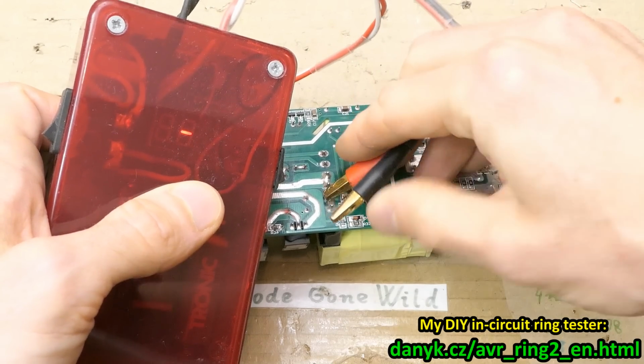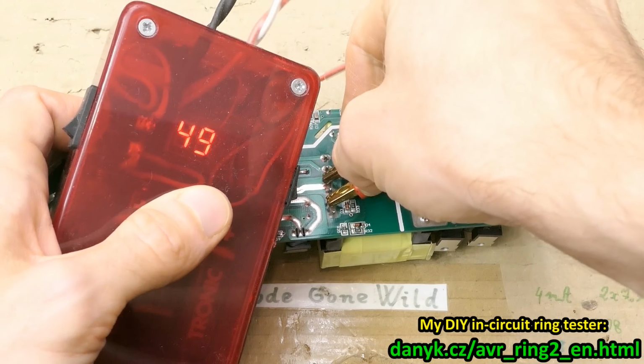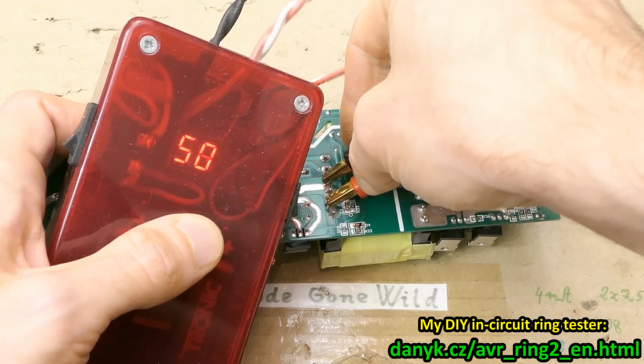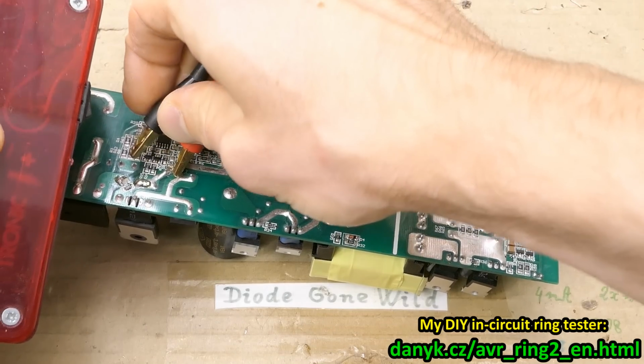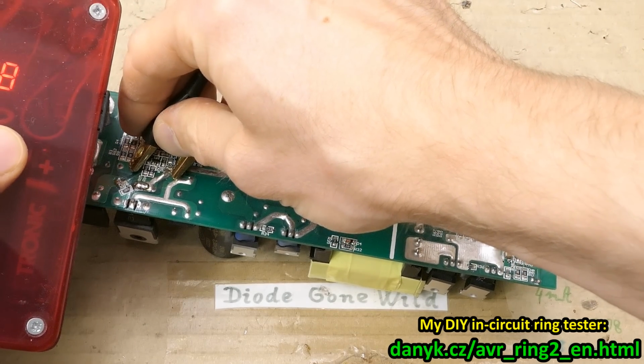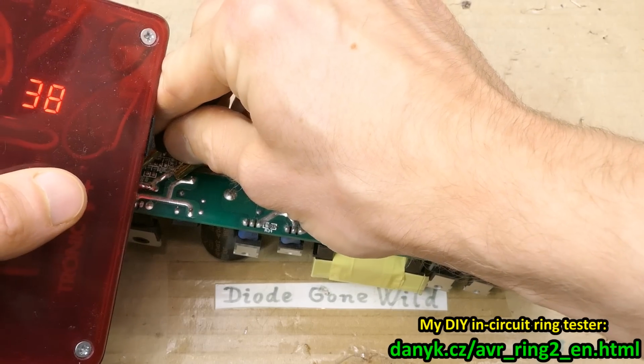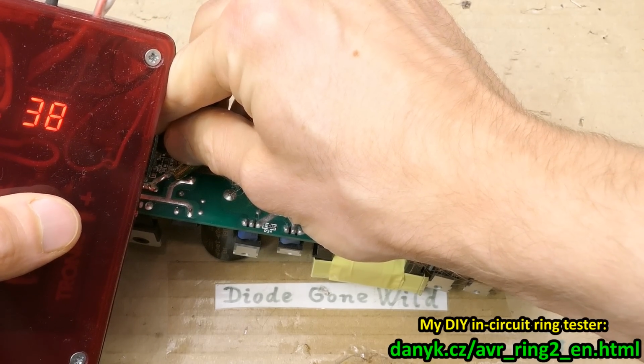This is to verify there are no short turns in the transformers, and this one shows a lot of rings, so it's not bad. I can also ring test the power factor correction inductor, also quite a lot of rings, not a bad inductor, no short turns in it.